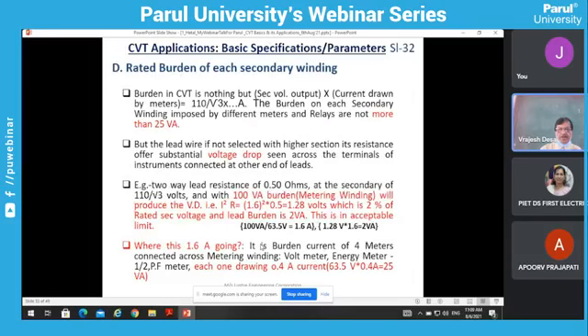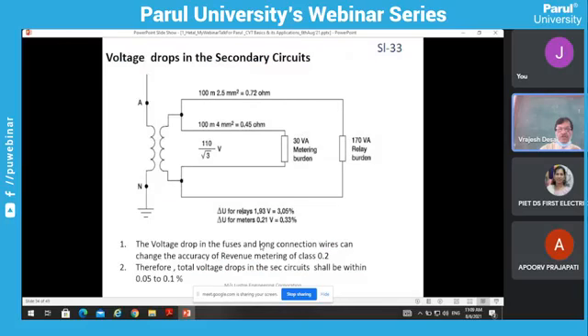Now rated burden. Normally rated burden, as we already discussed, is output voltage into the current which is drawn by the relays or meters. So here let us assume that, as you can see, 30 VA is for metering burden and 170 VA for relay burden. So the total simultaneous burden becomes 200 VA, right? Because both the burdens are connected in parallel, both will take the current separately depending on their VA requirement. That is the resistance impedance of the meters and relays.